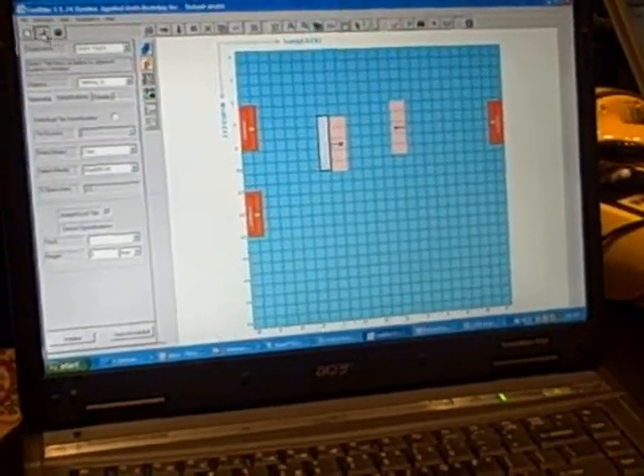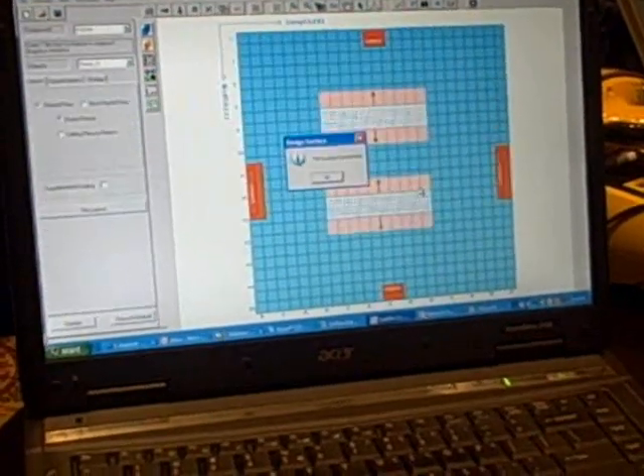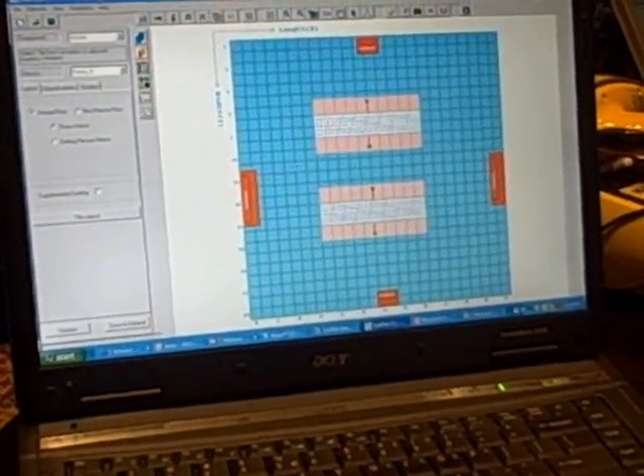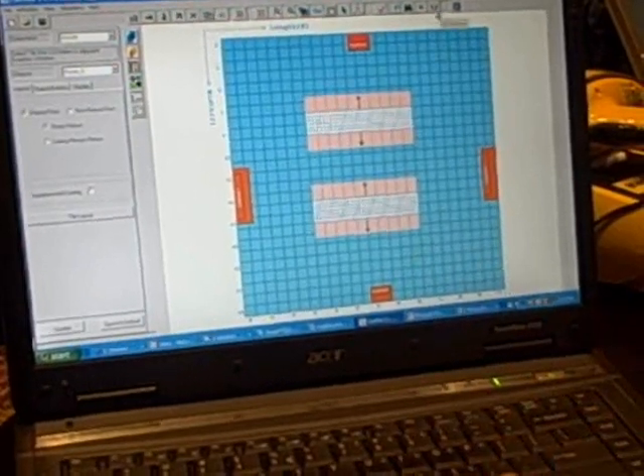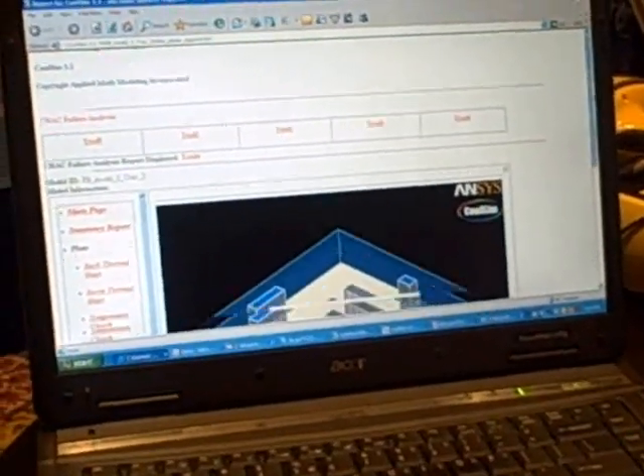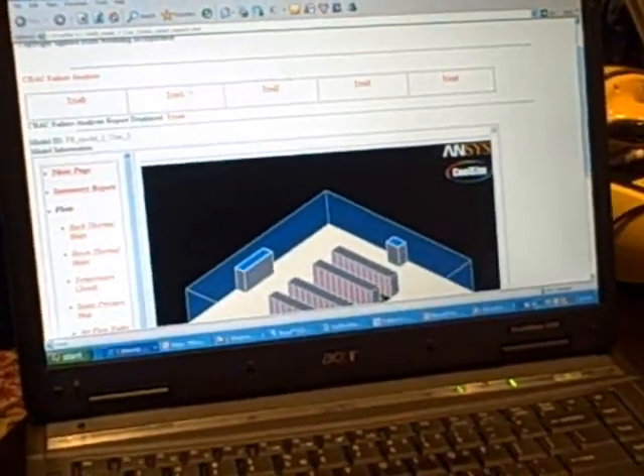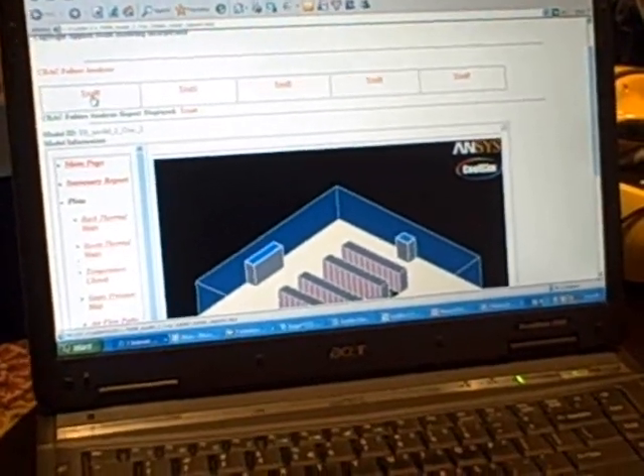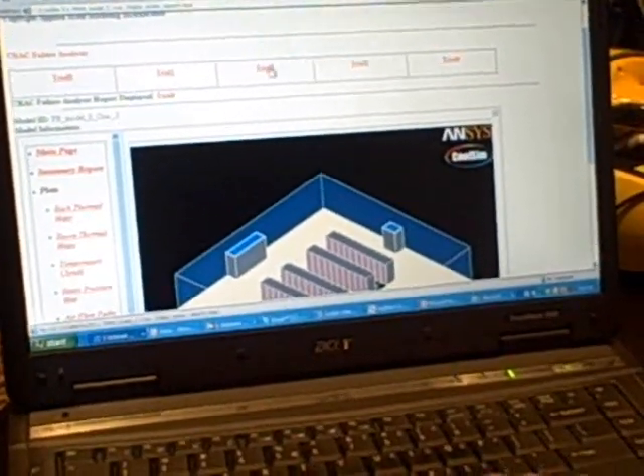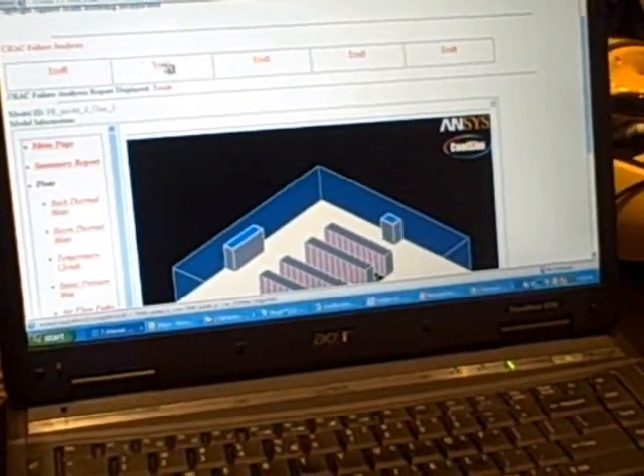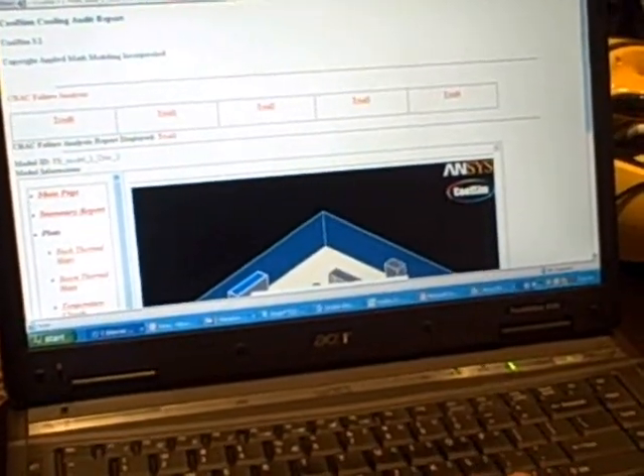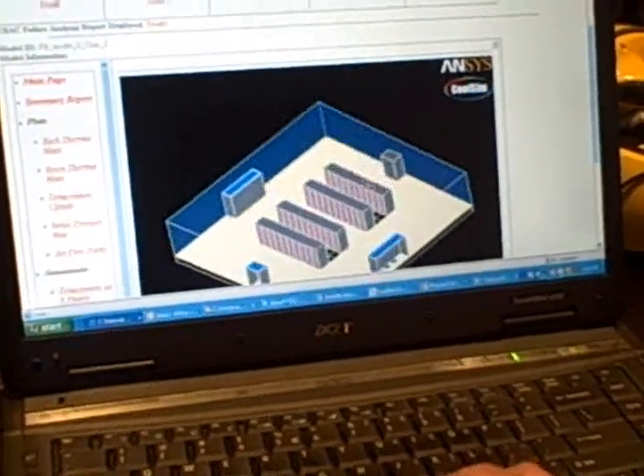For purposes of time today, I'll pick one that I've already run to show you what the output looks like. So here's a job that I've run. I've already submitted it, and I'm going to now take a look at the output. The output of the CoolSim application comes in the form of HTML reports, and you see here I've run five trials. Trial zero is with no CRACs off, and then I've gone around and shut each CRAC off individually using that tool I just showed you, the CRAC analysis.